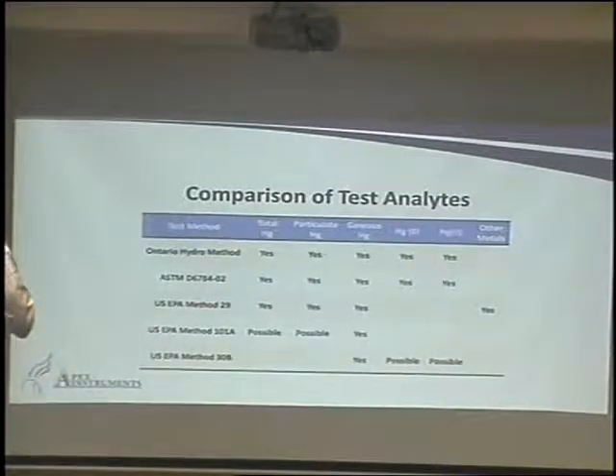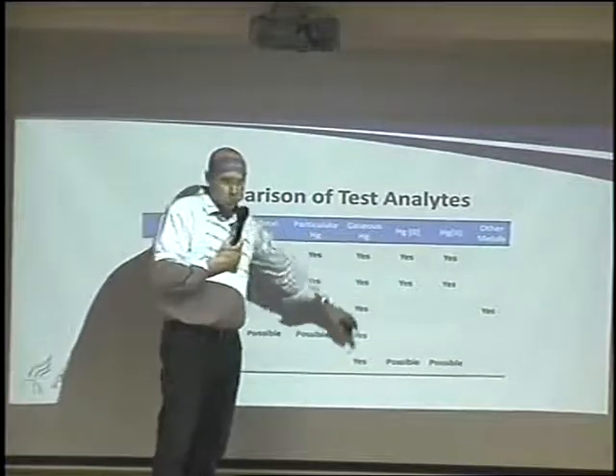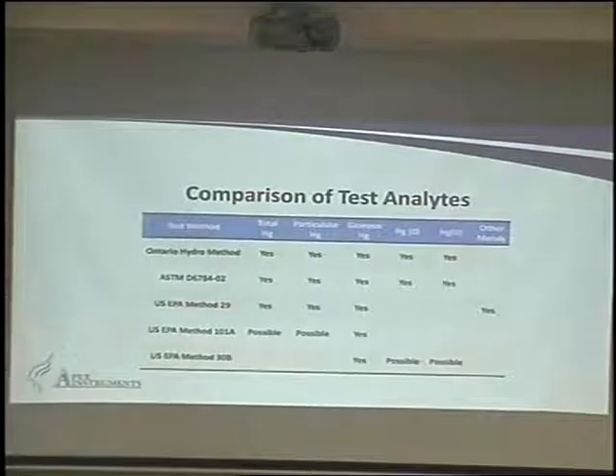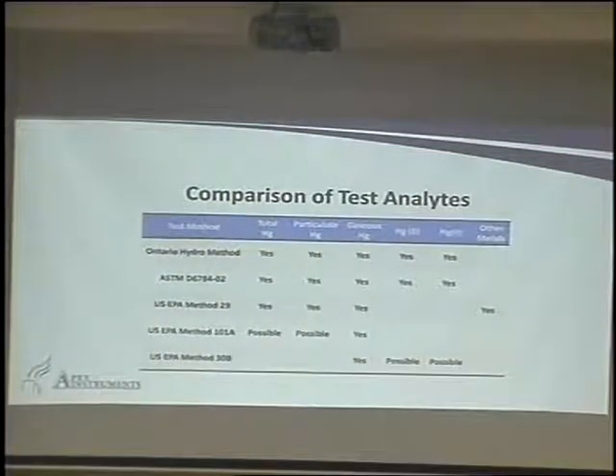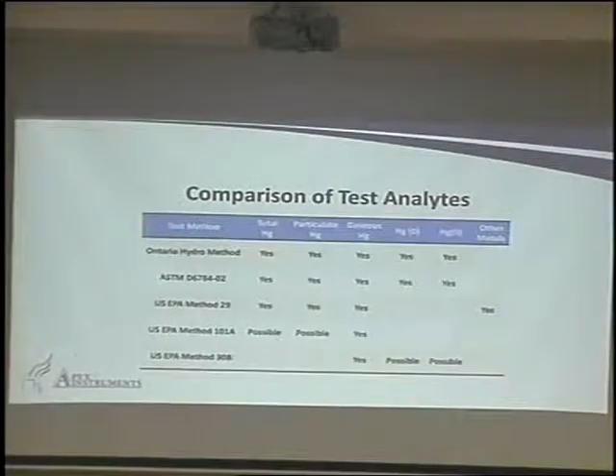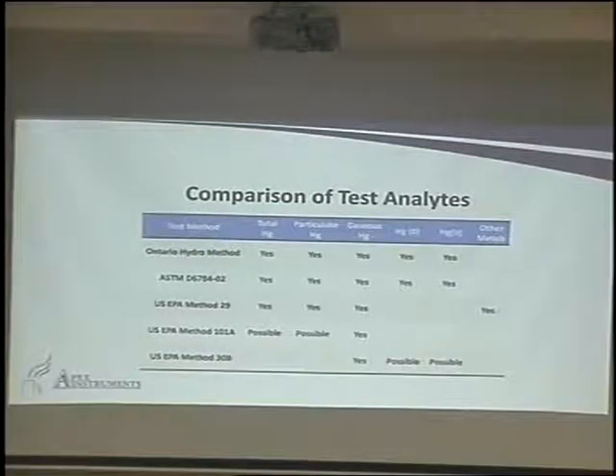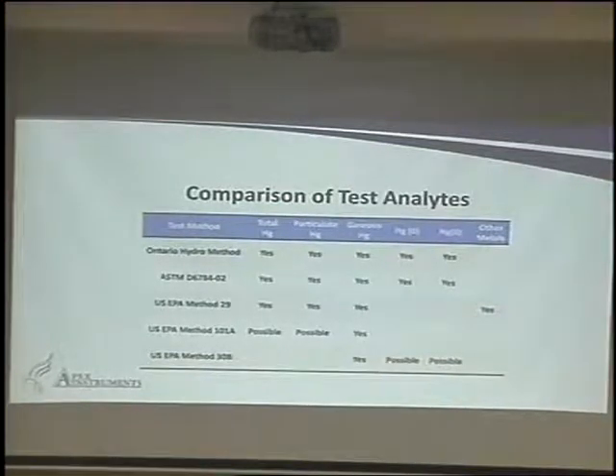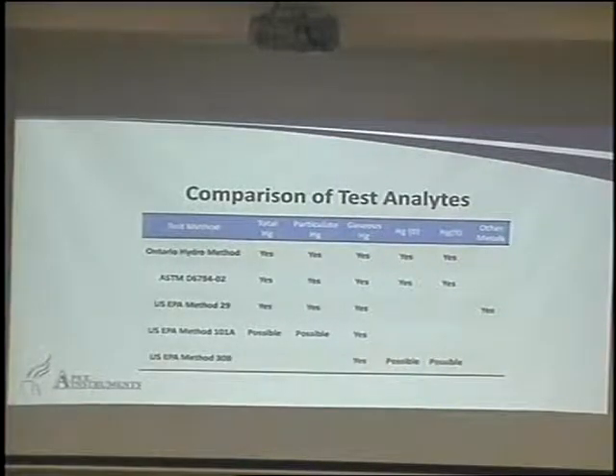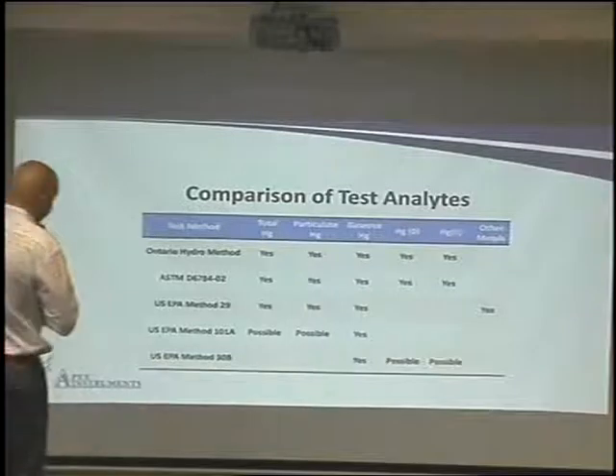So what we're looking at here more likely is our gaseous phase mercury, okay? We're looking for mercury in the gas phase that's being emitted out from the stack as a gas. We're not looking for particulate-bound mercury at all with this method. And we're not looking for any other metals here either. It's only going to do our gaseous here and our elemental mercury as well. We can separate the types of gaseous mercuries that we capture. Okay?